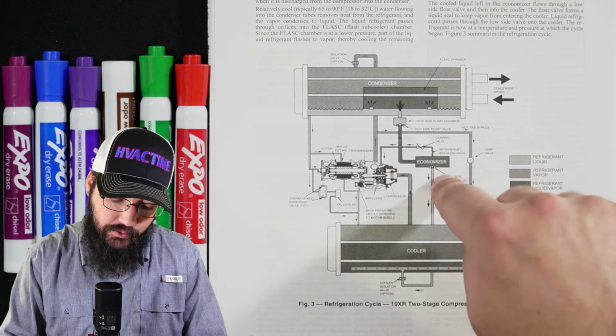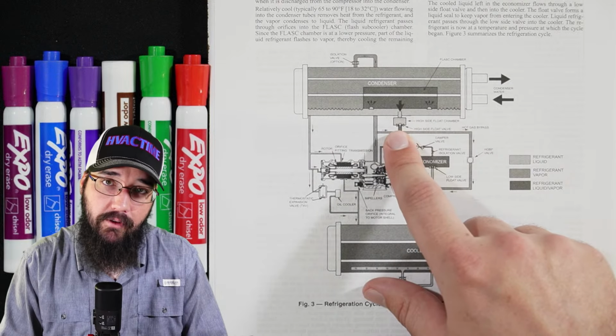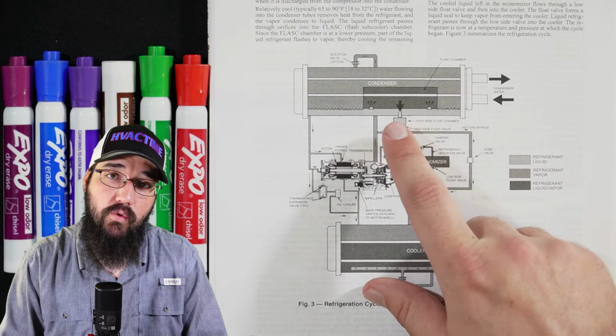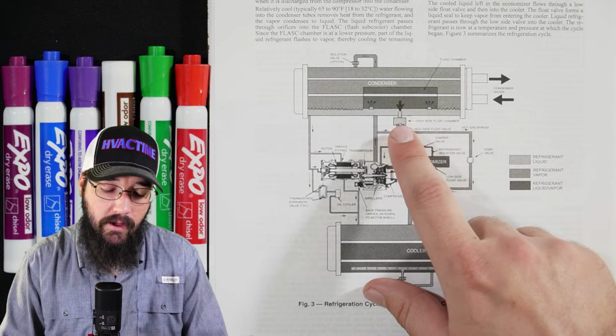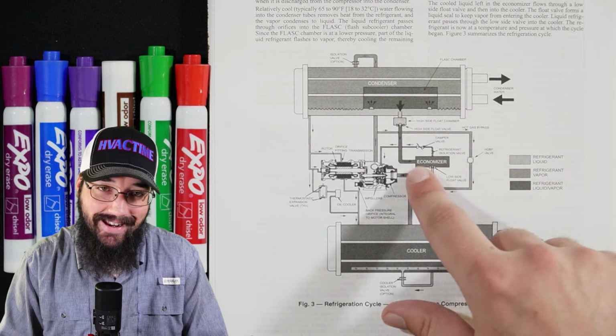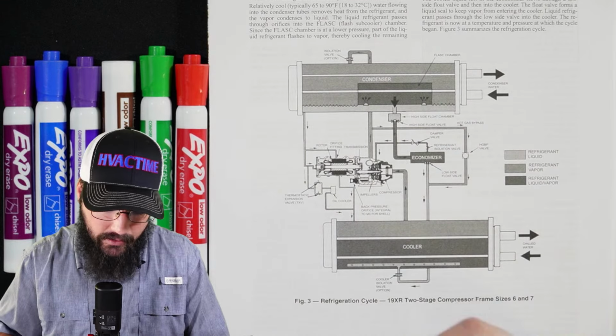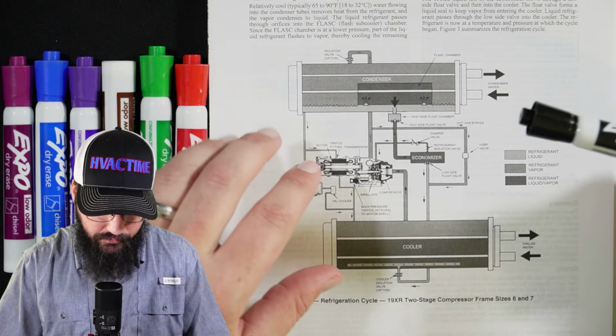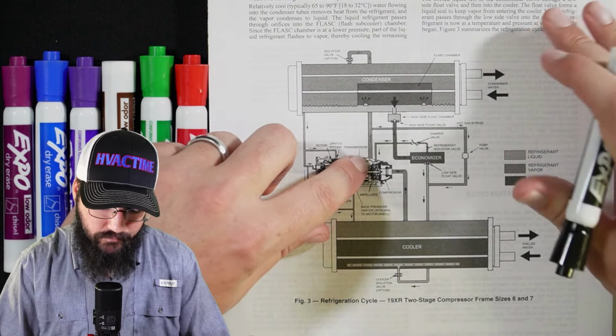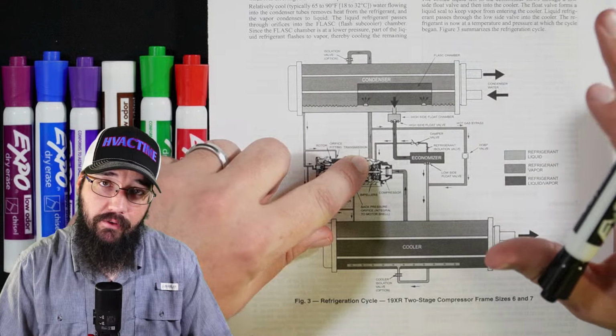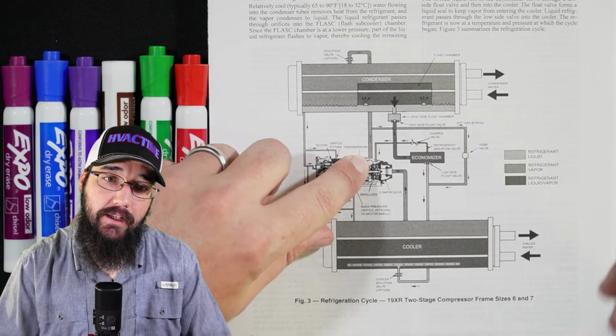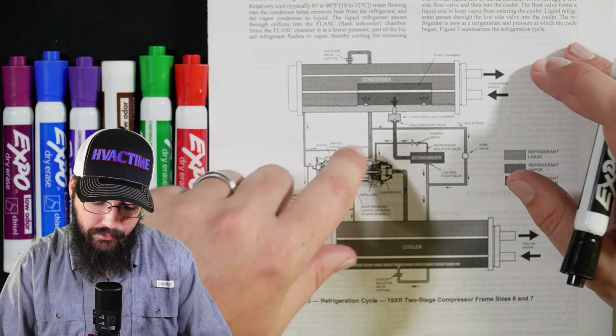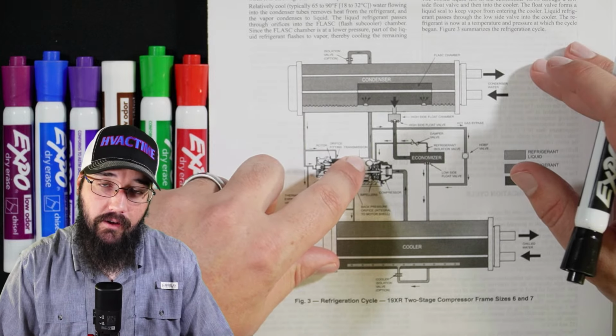But Carrier uses the same type of metering valve for the 2-stage or the single-stage compressor. The difference is whether or not it has the economizer. So let's get into our refrigeration circuit here. We're just doing a quick recap of how the circuit works in this machine, and then I'll roll into deeper on what that float valve is doing.